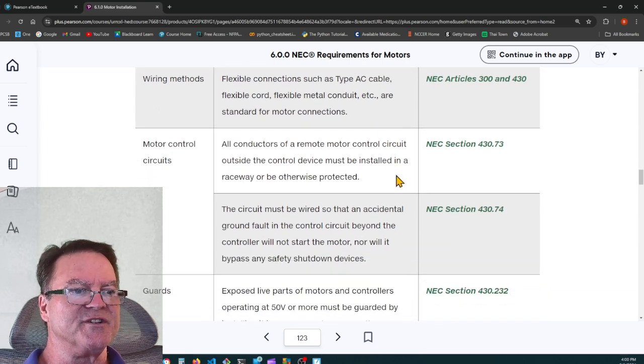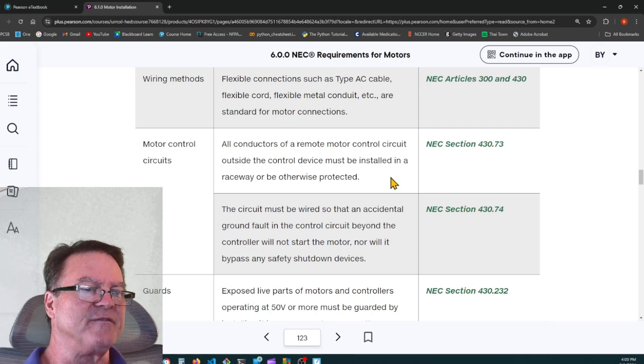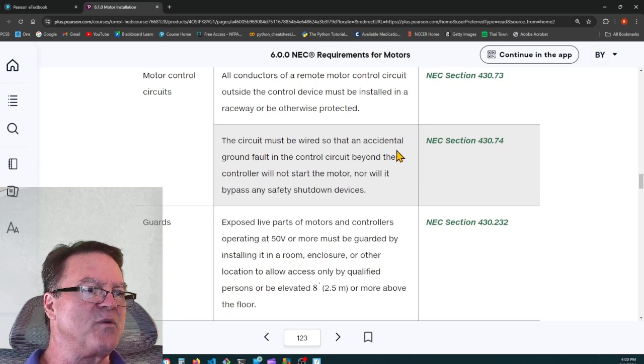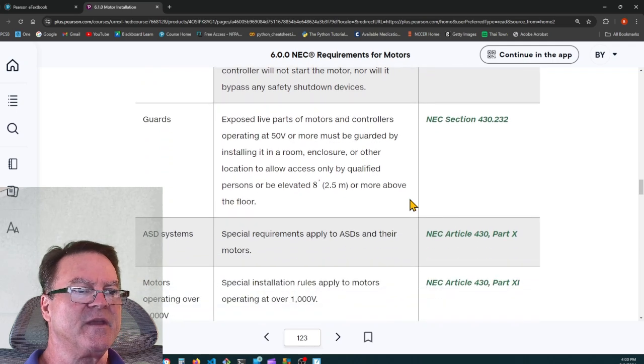You can't just pipe into them with rigid conduit or EMT. It has to be flexible. All conductors of a remote motor control circuit outside the control device must be installed in a raceway or be otherwise protected. The circuit must be wired so that an accidental ground fault in the control circuit beyond the controller will not start the motor, nor will it bypass any safety shutdown devices.